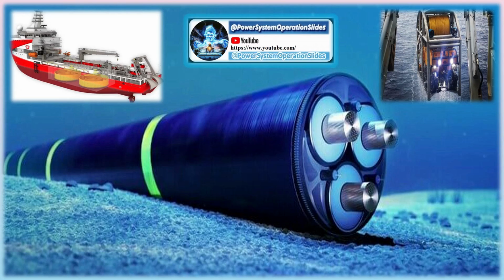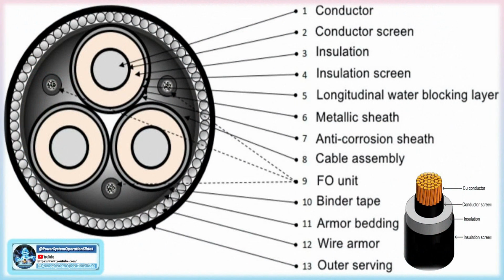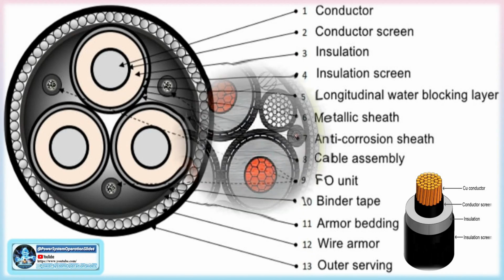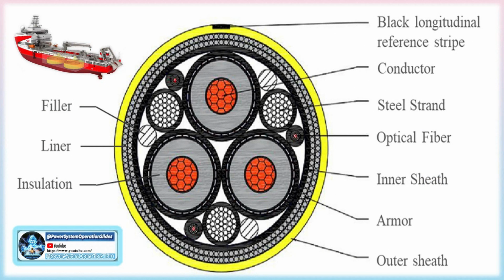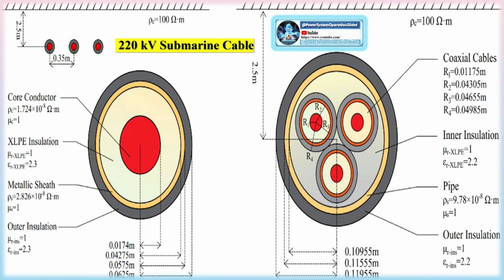Lead sheaths: in many high-voltage cables, a lead sheath is used to provide additional protection against water ingress. The lead layer acts as a barrier and is especially important for cables buried in deep water where extreme pressures exist. Armor: the armor in HV cables is often more substantial, sometimes involving multiple layers of galvanized steel or aluminum wires. This ensures that the cable can withstand the high mechanical forces experienced during installation and operation at great depths. HV cables often come in both AC and DC variants. High-voltage direct current (HVDC) cables are increasingly used for long-distance transmission due to their lower power losses over great distances.